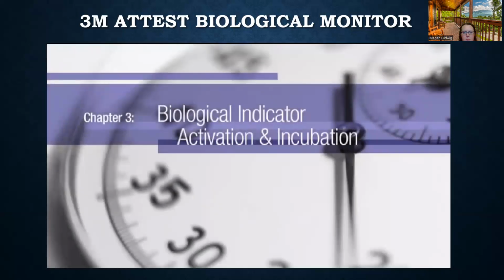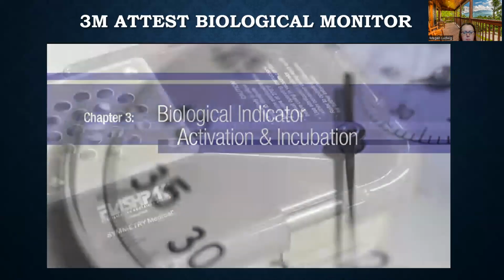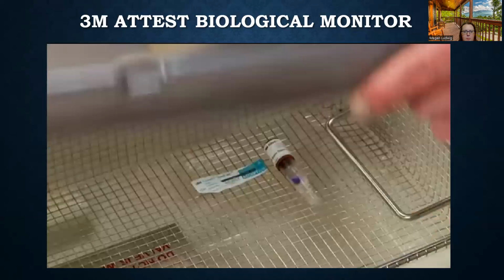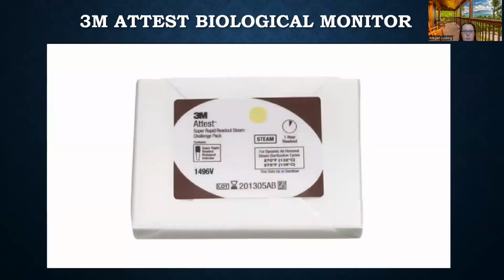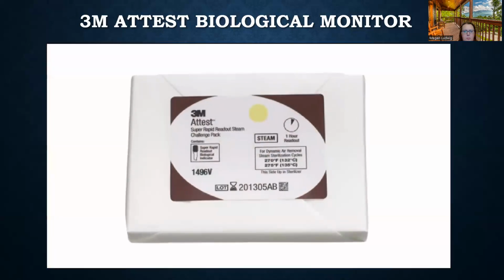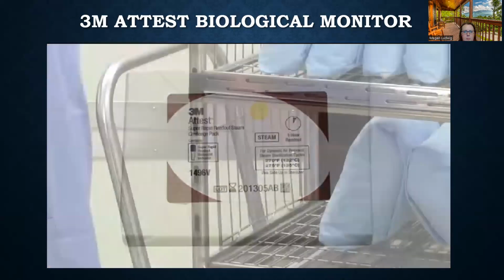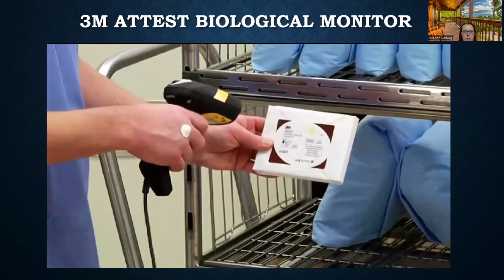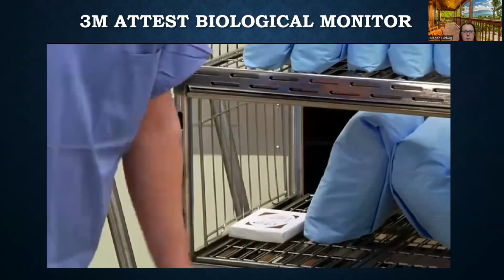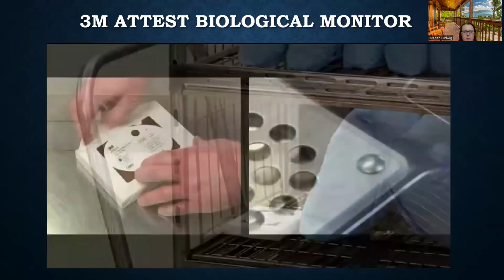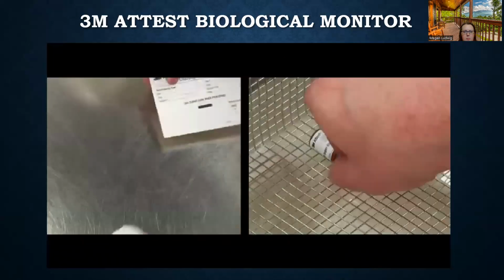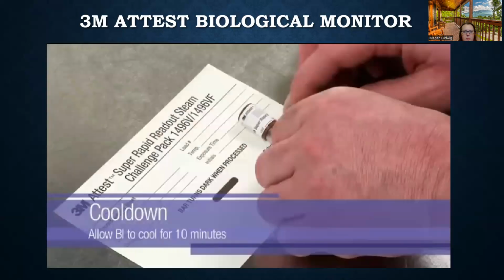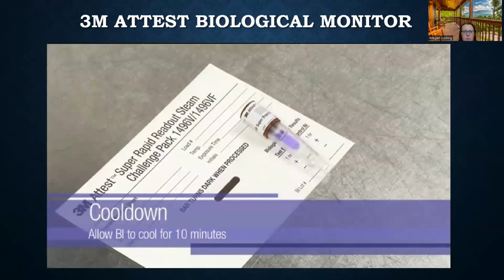Let's look at how to activate and incubate a super rapid BI in the Auto Reader 490. The first step is to remove the BI or challenge pack from the sterilizer. If using an Attest Super Rapid Readout BI challenge pack, if desired, scan the 2D barcode on the label to record product catalog number and lot code.